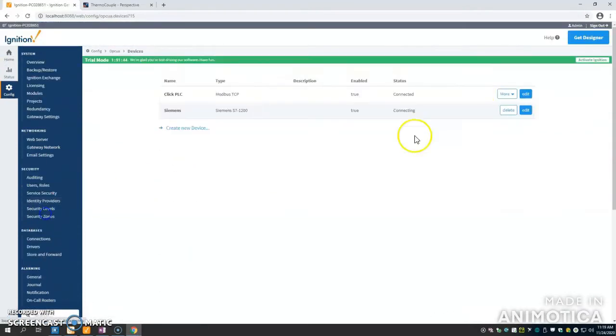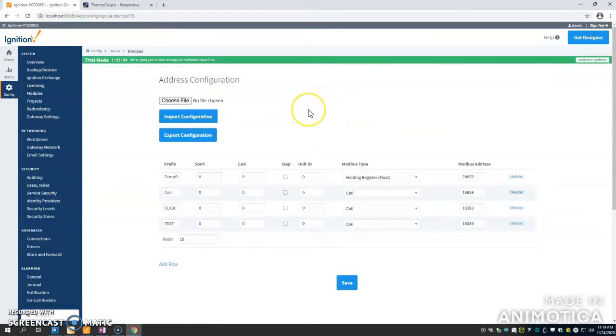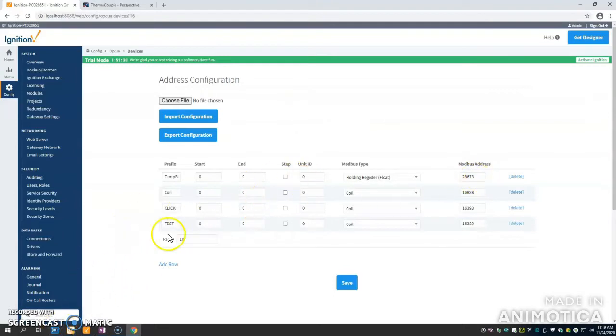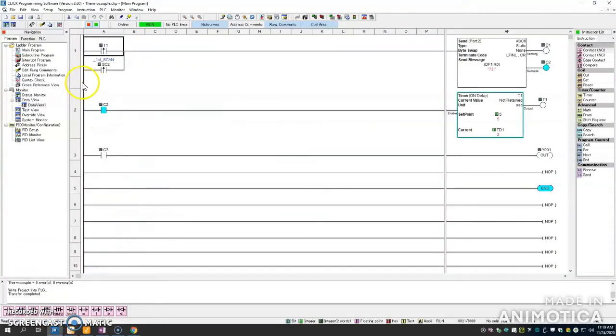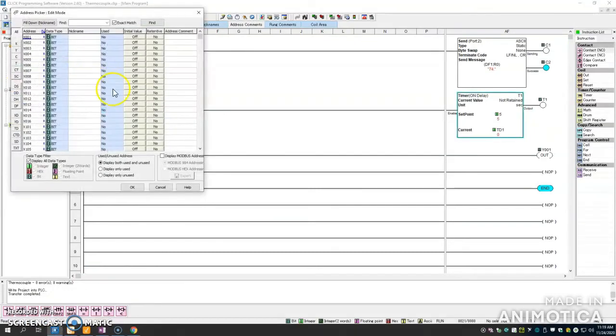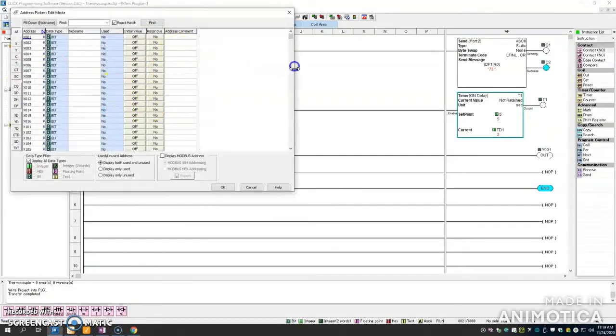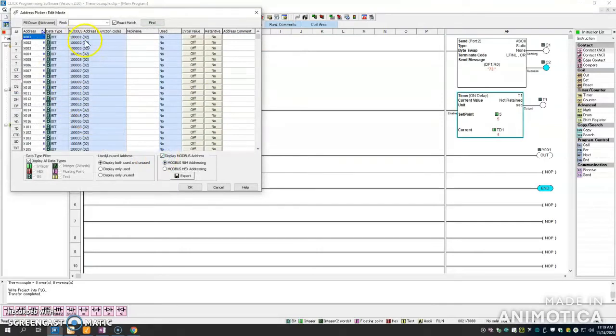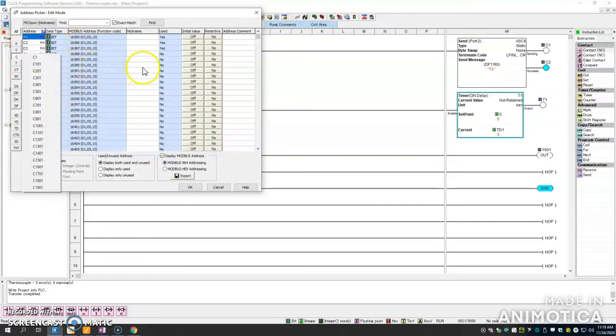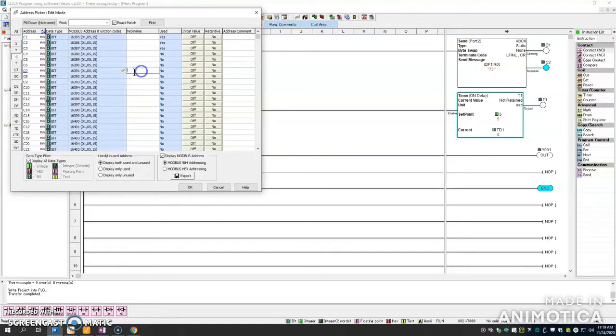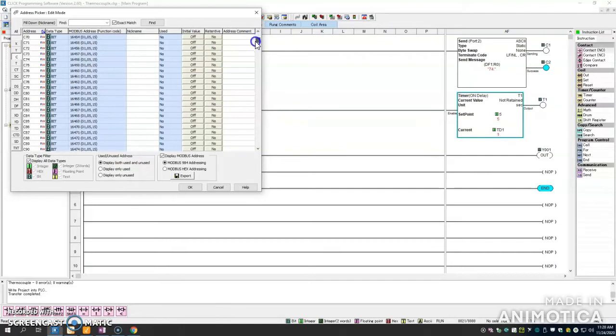But back to the device connections, Click doesn't support tag browsing, which means you can't just go through and pick out tags and look through all the tags. You have to import specific ones, so you have to do it via Modbus connections or Modbus address. If you go into Click software and drag it out, it'll display the Modbus address, so then you just plug the Modbus address in and make sure it connects, and then it should be easy. Then you can test it with a quick client and all that. It's fairly easy to navigate. This is the hardest a PLC is going to be, because an Allen-Bradley or a Siemens would be plugged in a lot easier, they interface better.